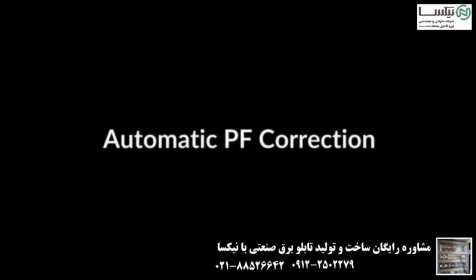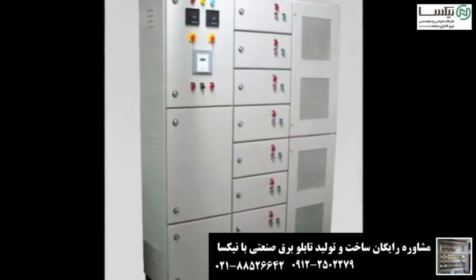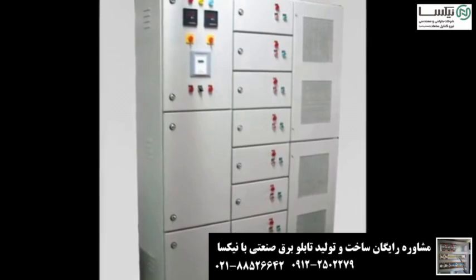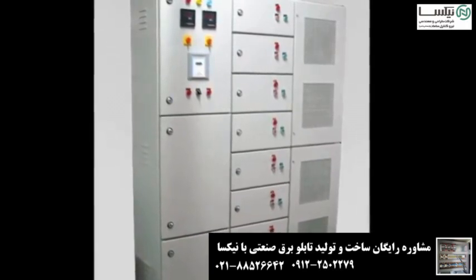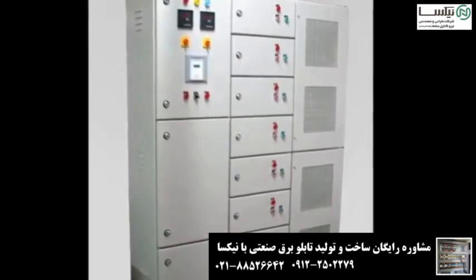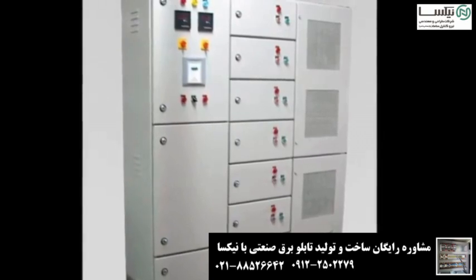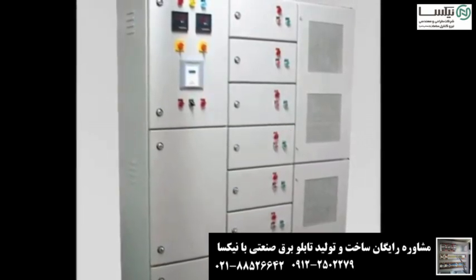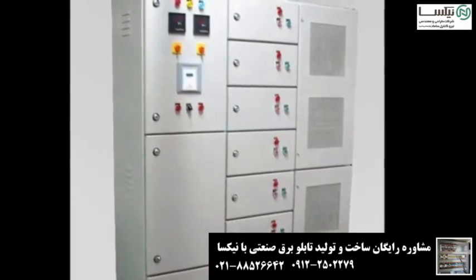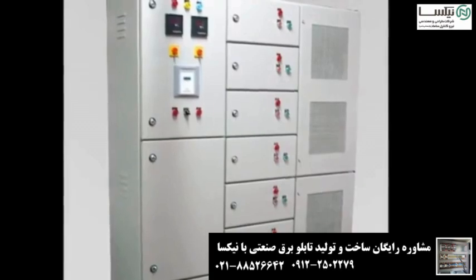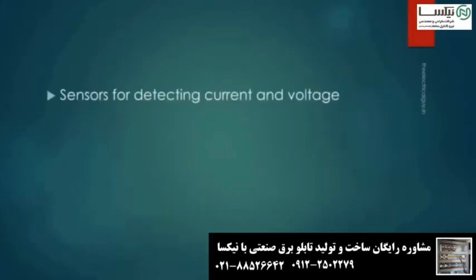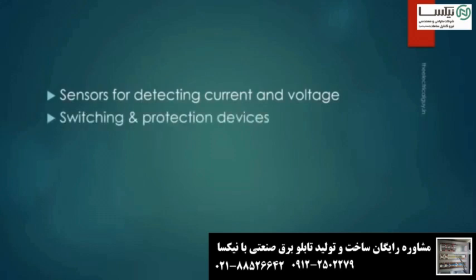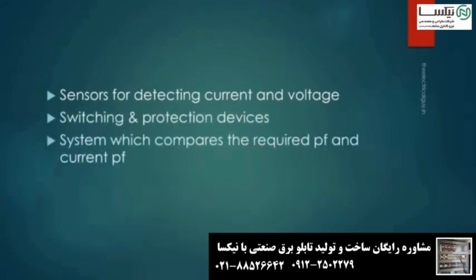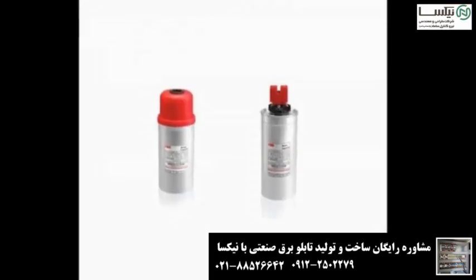Automatic power factor correction. In most systems, there is not a constant absorption of reactive power because of the working cycle of the equipment. In such installations, there are systems for automatic power factor correction which allow the switching of different capacitor banks when needed. This type of automatic power factor control panel, or APFC panel in short, consists of sensors for detecting current and voltage, switching and protecting devices, an intelligent system which compares the required power factor and the current power factor, and of course the capacitor banks. These types of panels are widely used.